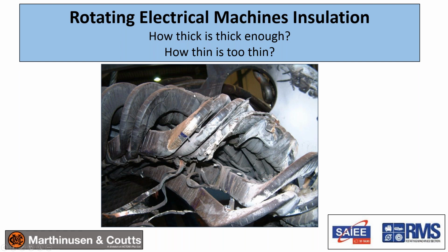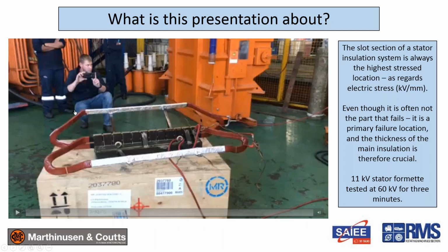My apologies. Okay. This is an 11 kV stator coil undergoing a high voltage test. It should have been a destructive high voltage test. It was at 60 kV. It took the full 60 kV for the full 3 minutes. And in the video, you see a lot of tracking on the overhang and no failure in the slot. So the point I was making is that you have a very high electric field stress inside the slot, yet that doesn't fail, and you get arcing and tracking on the overhang.